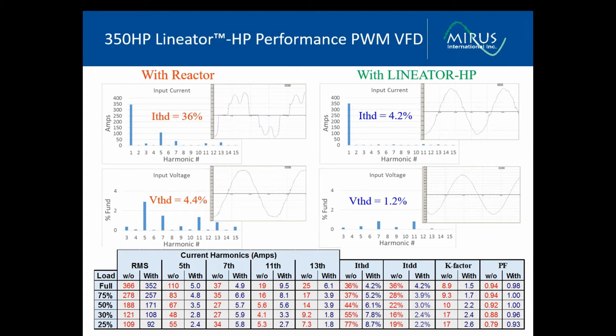These measurements show the operation of a 350-horsepower variable speed drive equipped with a line reactor. Current distortion was 36%, predominantly fifth and seventh harmonics. Voltage distortion was 4.4%, again with the 5th, 7th, 11th, and 13th as the predominant harmonics.